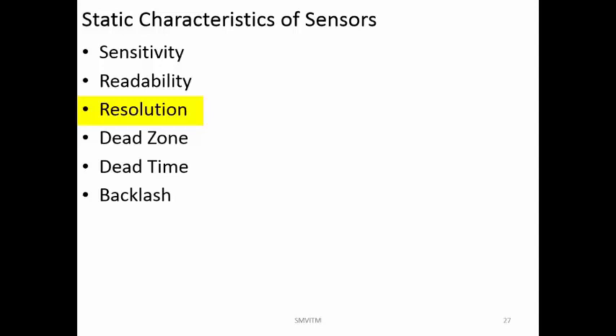So you have to always see what the resolution and what the accuracy of that particular device is. Combined, you will know the performance or the capability of that instrument. You should not have a device with a resolution of say 0.1 volt but an accuracy of plus or minus 1 volt. Then that is more or less completely useless. So you have to always see resolution and accuracy together.